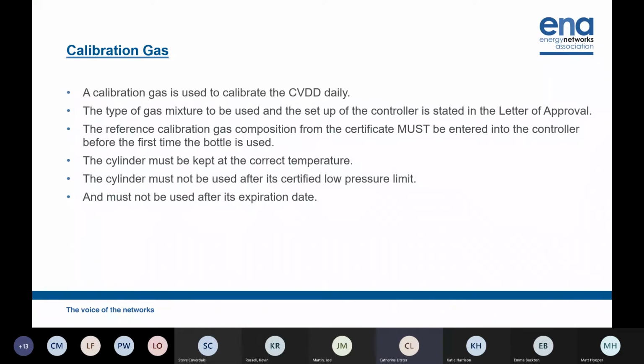If you go to site and change that calibration gas, then the reference calibration from the certificate must be entered into the controller. This is done before the first time the bottle is used. If you don't update the calibration details and ensure they're correct, the next day you go to use that bottle, it will be unusable, and that will be a loss of record, and that could cause CV shrinkage in the future. A few other details: the cylinder must be kept at the correct temperature. It can't drop below 10 degrees. It must not be used after the low pressure limit, in most cases 4 bar. And it must not be used after its expiration date.